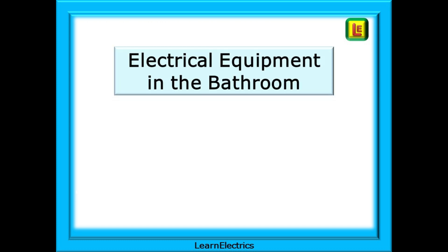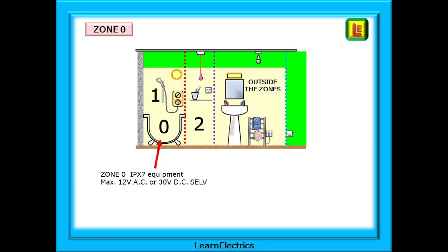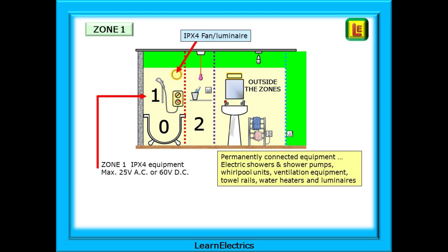What electrical equipment can we install in the zones? What IP ratings and voltages? Starting with zone 0 inside the bathtub: only IPX7 equipment is permitted. Voltages are limited to a maximum of 12 volts AC and 30 volts DC — just a quarter of the normal extra-low voltage limits.